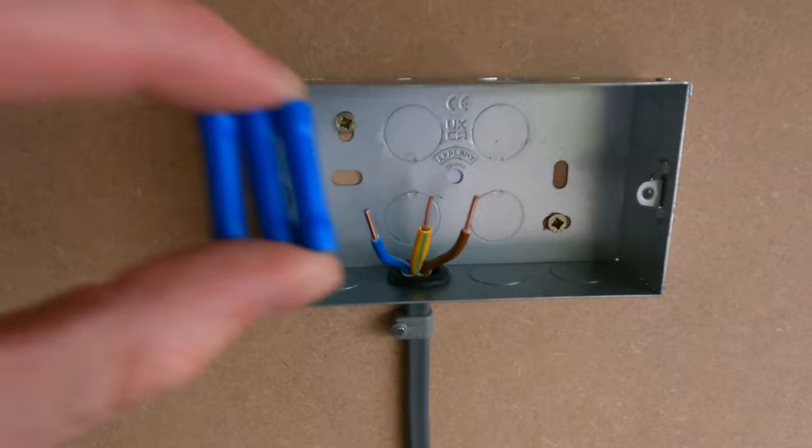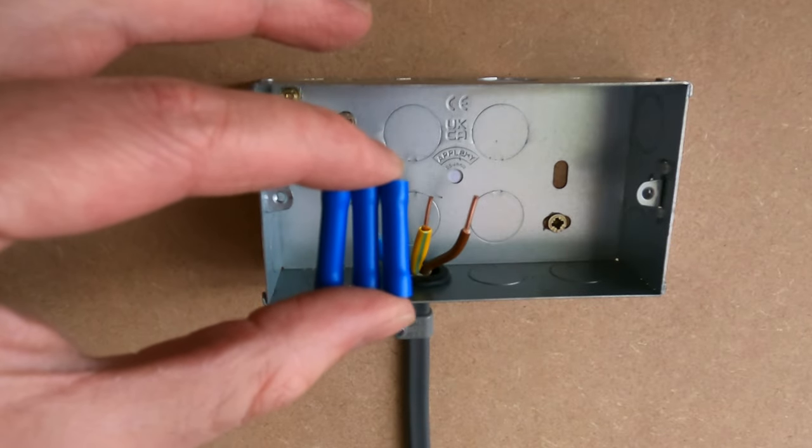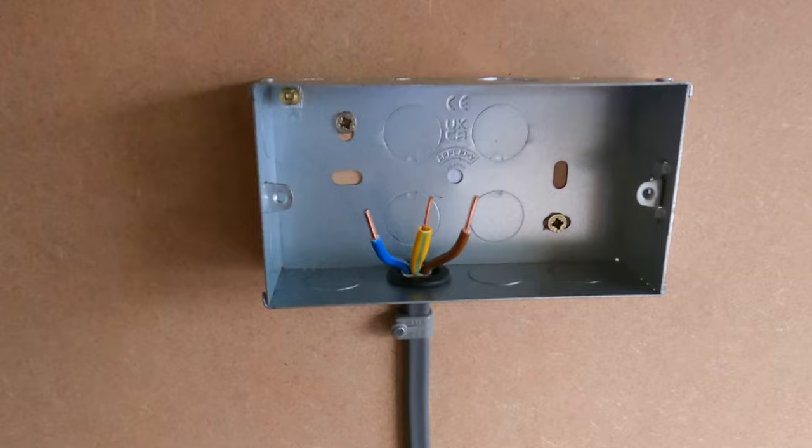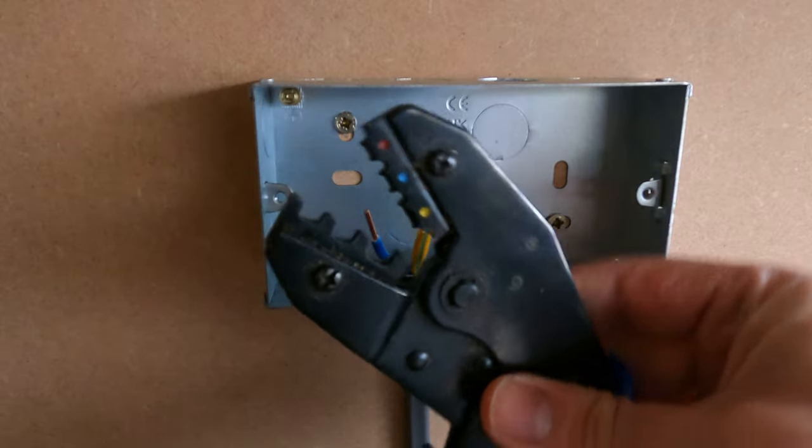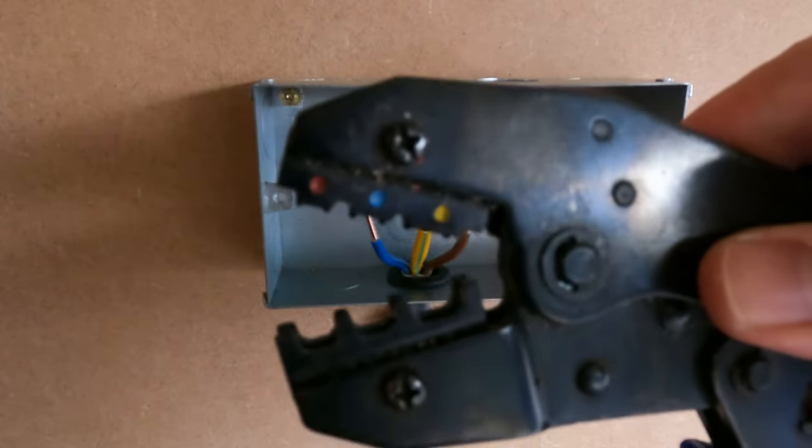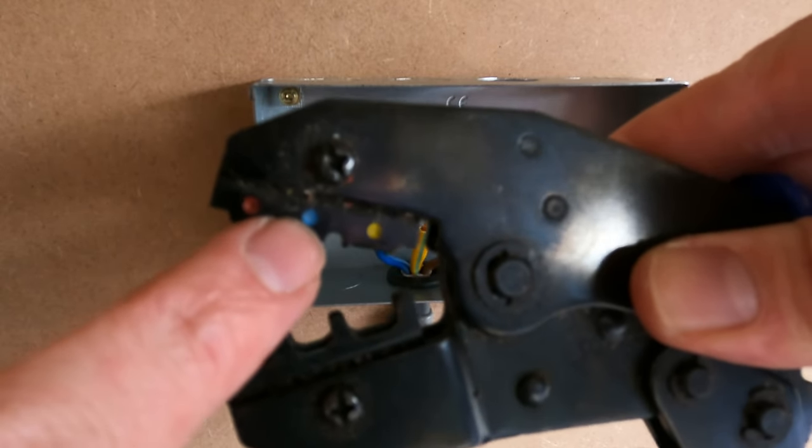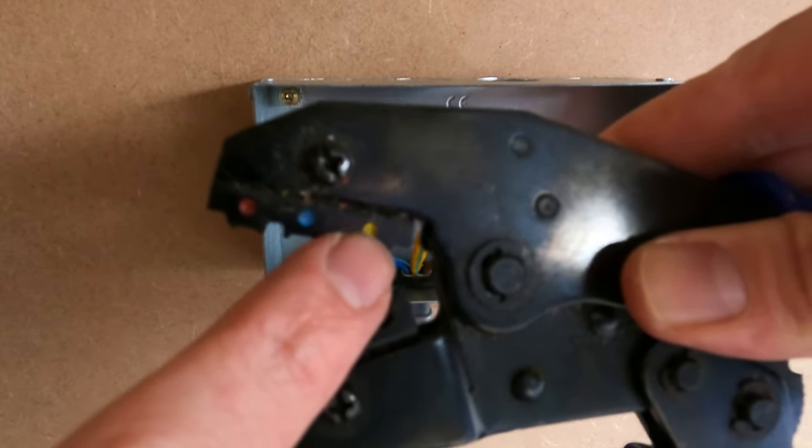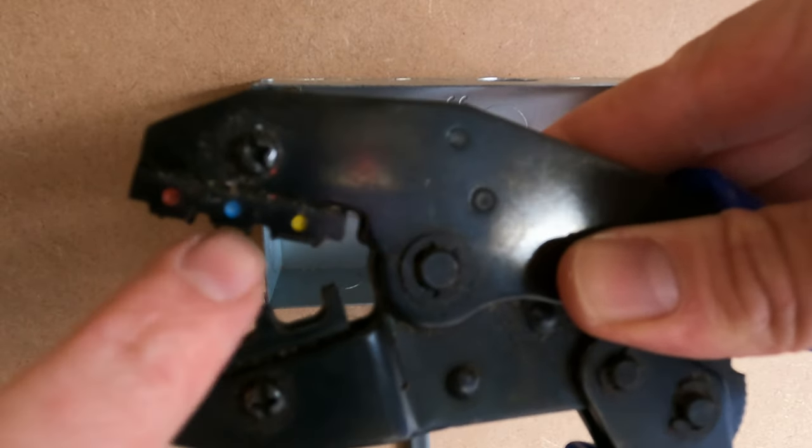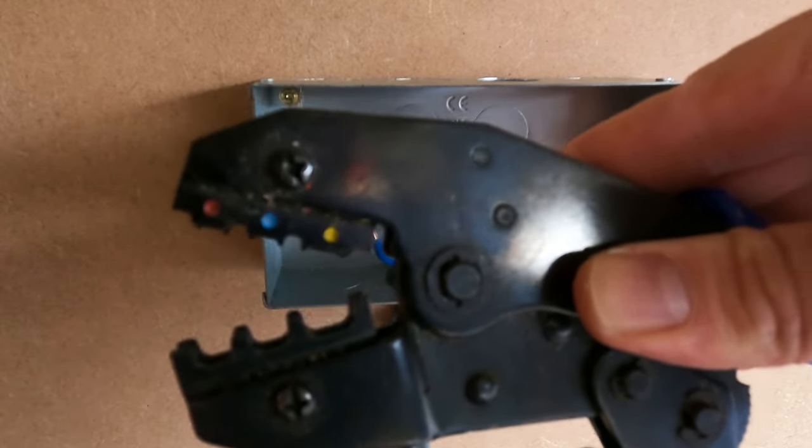So you get various size crimps, we're going to be using the 2.5 mil crimps for the 2.5 mil cable. Then you want to grab your crimping tool. So you've got various different slots here, the red one is for the smaller cables, the blue one for the cable we'll be doing, a 2.5, and a yellow for the larger size cables. And like I say, we'll be using the blue slot today.